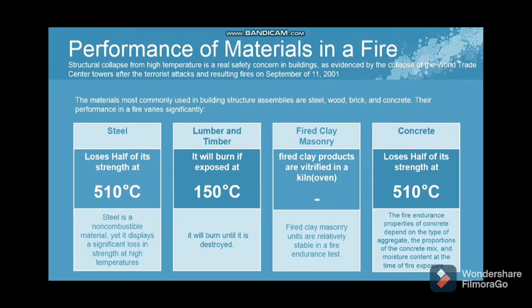Next is lumber and timber. It will burn if exposed at least 150 degrees Celsius. It will burn until it is destroyed. For fired clay masonry, fired clay products are vitrified in a kiln or oven. Fired clay masonry units are relatively stable in a fire endurance test. And lastly, concrete loses half of its strength at 510 degrees Celsius. The fire endurance properties of concrete depend on the type of aggregate, the proportions of the concrete mix, and moisture content at the time of the fire exposure.